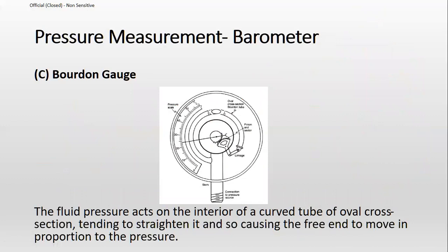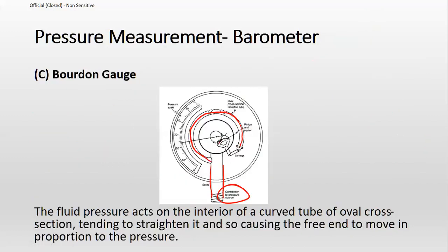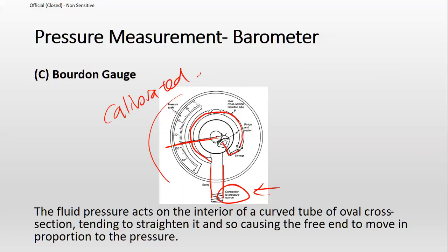Another device is the Bourdon gauge. The concept is simple: a stem connected to your pressure source is connected to a Bourdon tube, which is then connected to a mechanical linkage that moves a needle. Whatever pressure is exerted causes movement of the Bourdon tube, which causes the linkage to move the needle. The pressure scale must also be calibrated — by looking at the movement, we know the pressure.